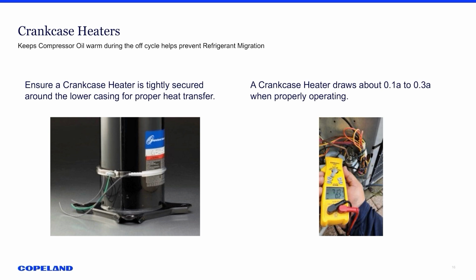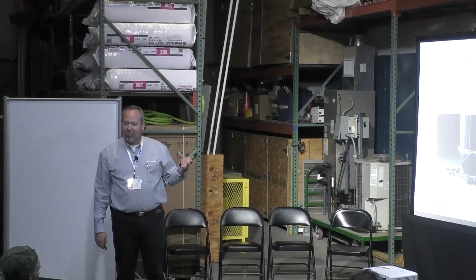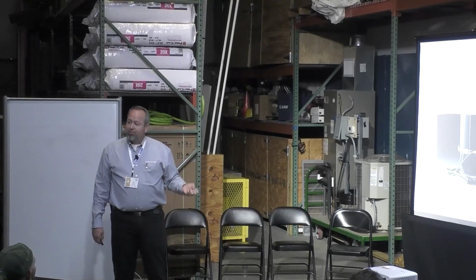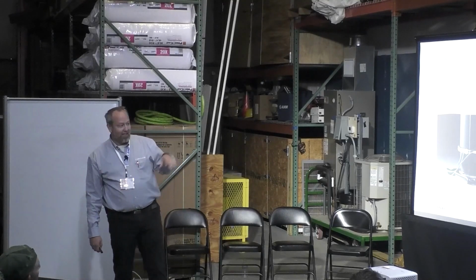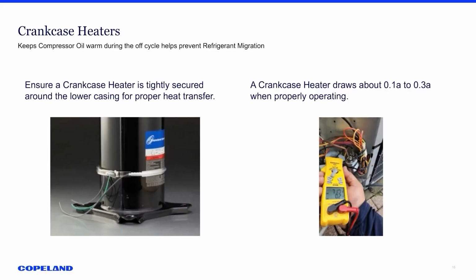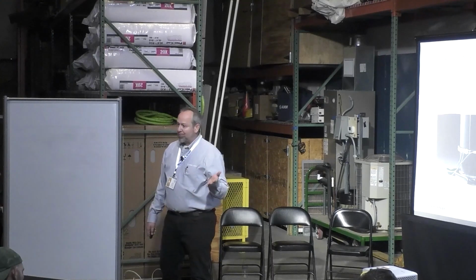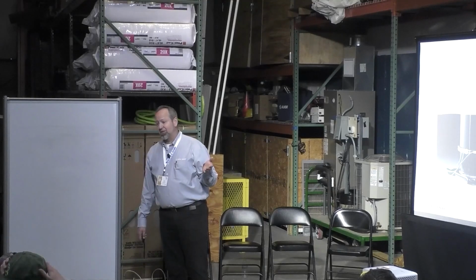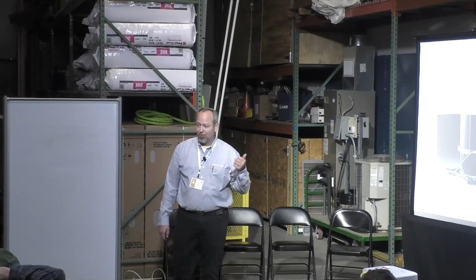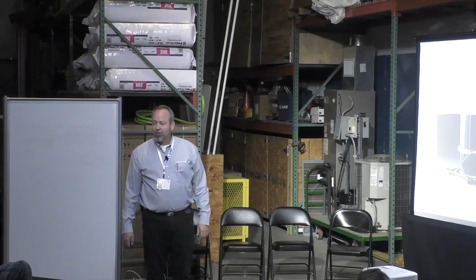That's where the oil is going to reside. That's where you want to keep that oil warm, as well as the base of the compressor, so that you have that refrigerant vaporizing and not sitting in that area in liquid form. What are you looking to draw? Somewhere about 0.1 to 0.3 amps is what your average crankcase heater is going to pull. So if you don't have that as a part of your regular maintenance program, especially for heat pumps, I would recommend that you add this for any heat pump PMs that you're doing out there in the field.